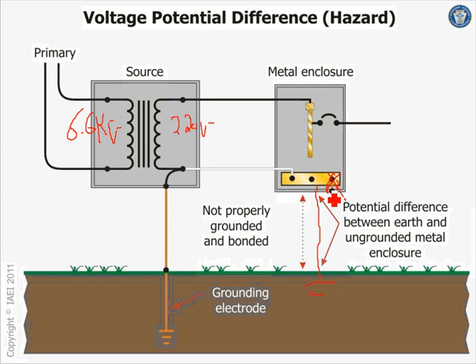So then you depend on the ground fault going right through Mother Earth to clear it. Now in the US, if your system is grounded or ungrounded, you must provide another alternative to ground your equipment. So this is an unacceptable means to bring a power system, from a grounded system or ungrounded system, to your building without establishing at your building a reference to the ground through tying your equipment to Mother Earth.